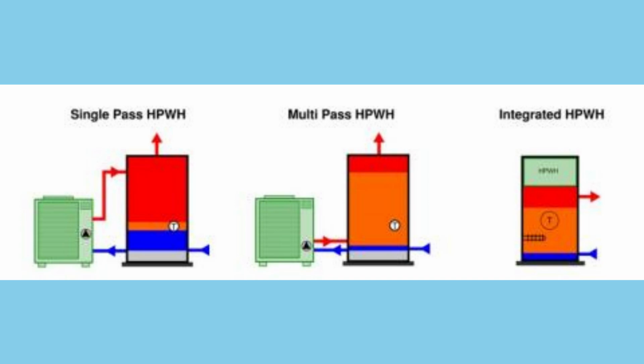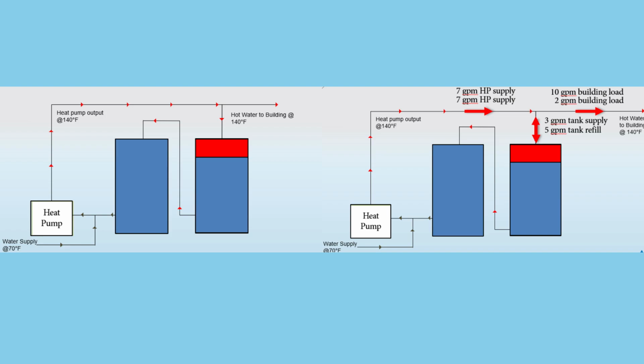But in multifamily buildings with high circulation loads, the onboard electric resistance heaters fire too often, lowering efficiency. For that reason, they're best used where there is no circulation loop. Finally, stratification is critical for single-pass heat pump water heaters. Cold water needs to stay at the bottom of the tank, while hot water is stored at the top.